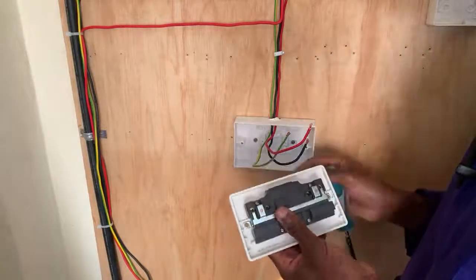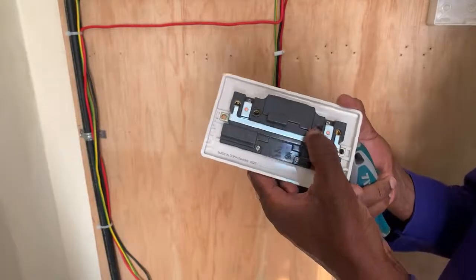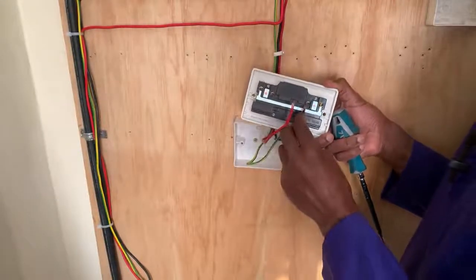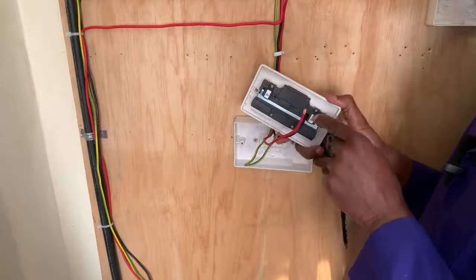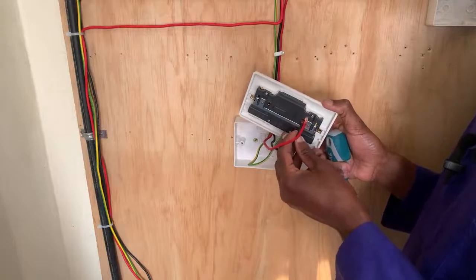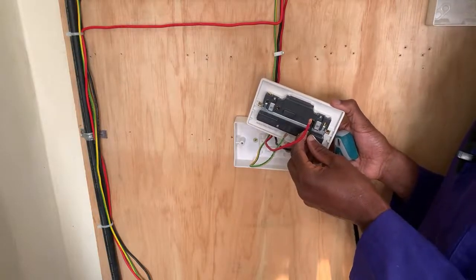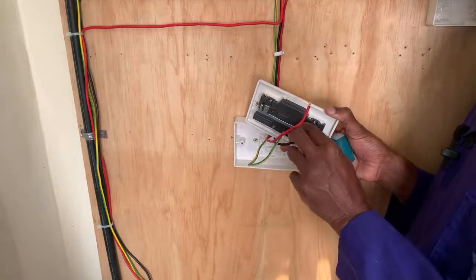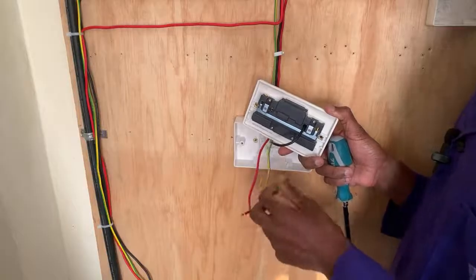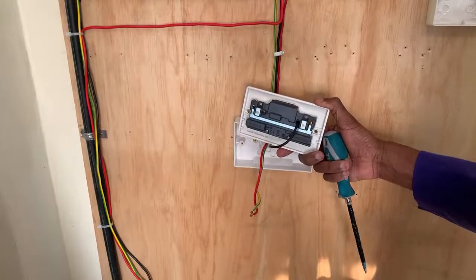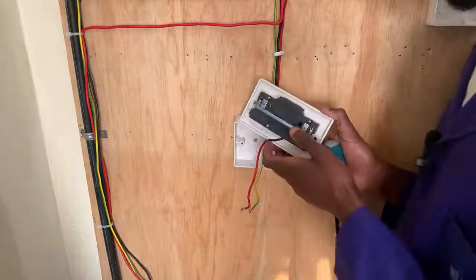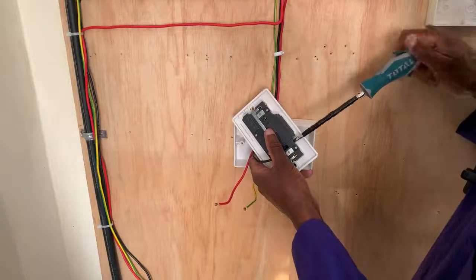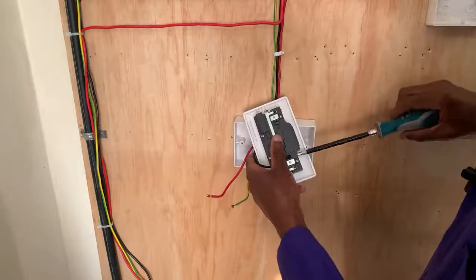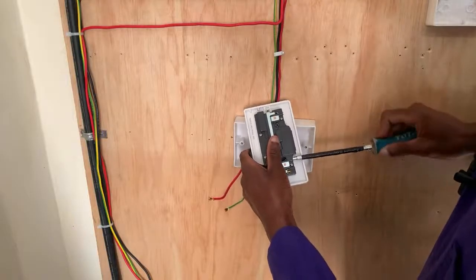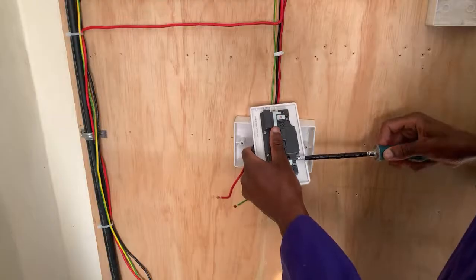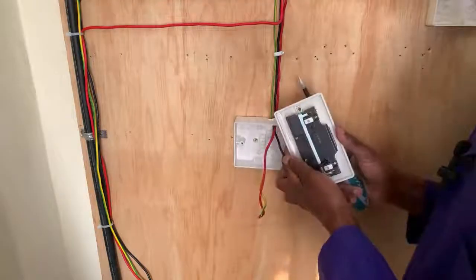So for my neutral, marked N, I connect my black wire there. Notice I haven't left the wire exposed, but made sure it goes all the way in. Another mistake people make is to screw onto the insulation, so I've allowed the cable to go fully in, and when I screw it, I ensure I'm screwing onto the copper wires, not the insulation. Then I tighten it to make sure it's secure.